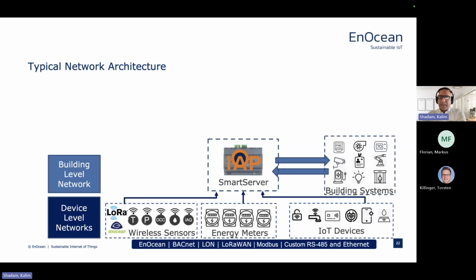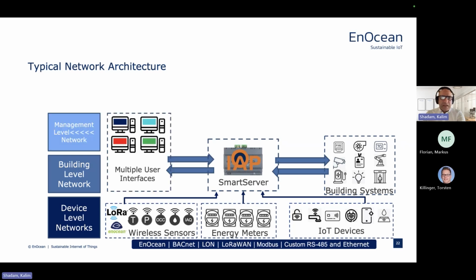We can connect directly into building automation systems, and this communication is bi-directional—into HVAC systems, lighting systems, fire and life safety systems, etc. We also have bi-directional communication at the management level network with multiple user interfaces, such as your supervisory building management system or SCADA system controlling and managing those systems through a graphical user interface.